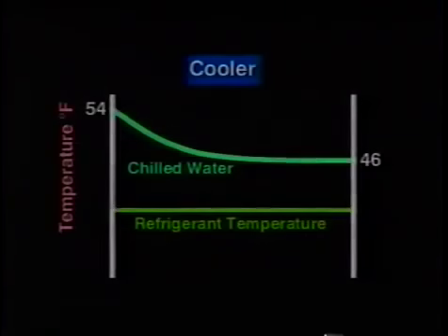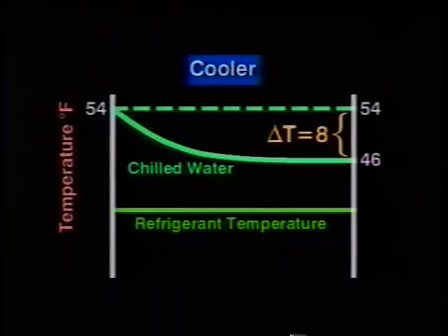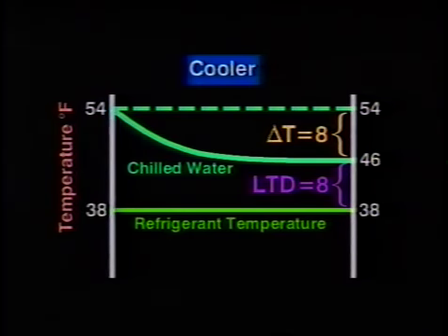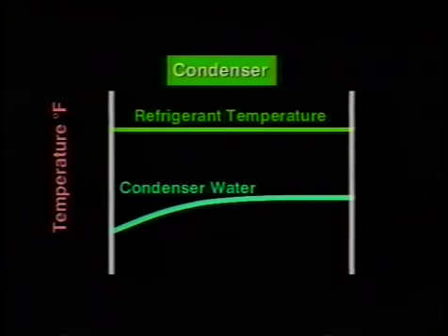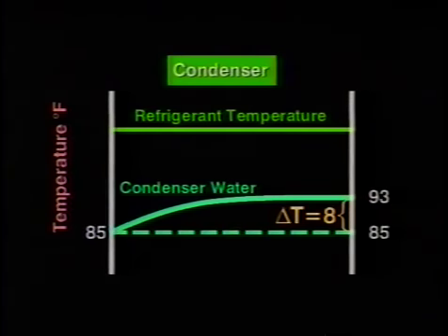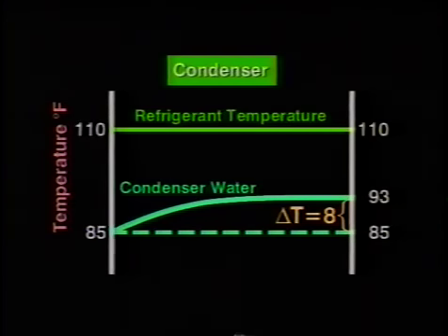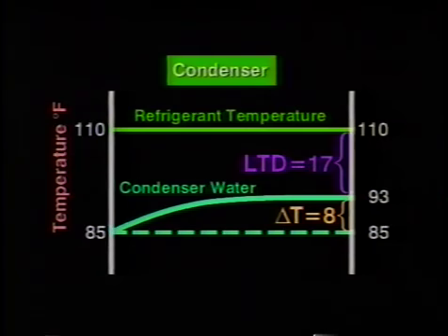The complaint is again low capacity. Looking at the chilled water in and out, this time we have a delta T of 8 degrees Fahrenheit instead of 10 degrees. The saturated cooler temperature is running high at 38 degrees. The cooler LTD is normal at 8 degrees. The condenser water in is normal at 85 degrees Fahrenheit, but is leaving at only 93 degrees. So our delta T is low at 8 degrees. The saturated condensing temperature is 5 degrees high at 110 degrees, and the LTD is 17 degrees, which indicates that our heat transfer is being impeded.